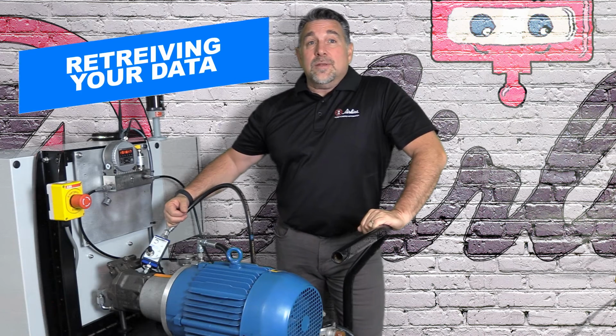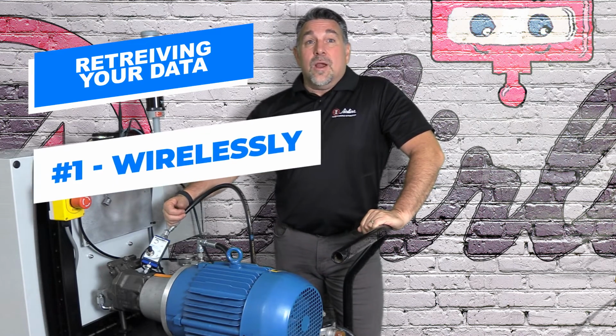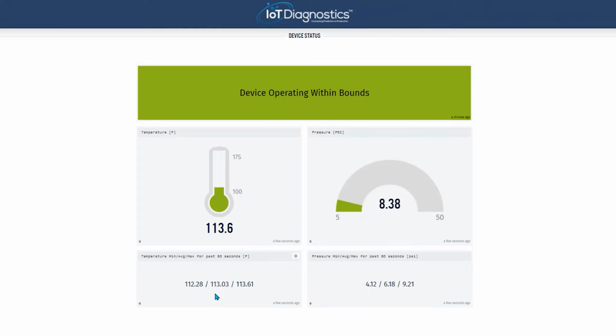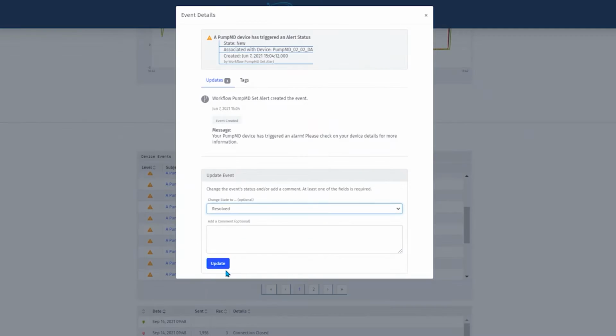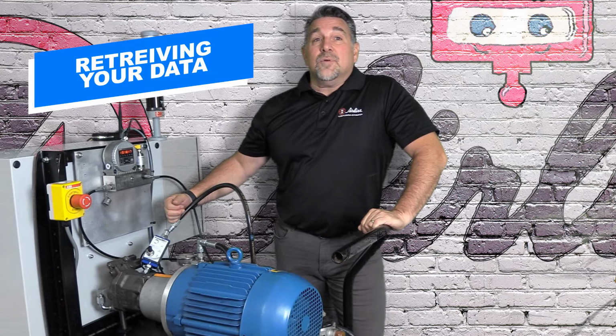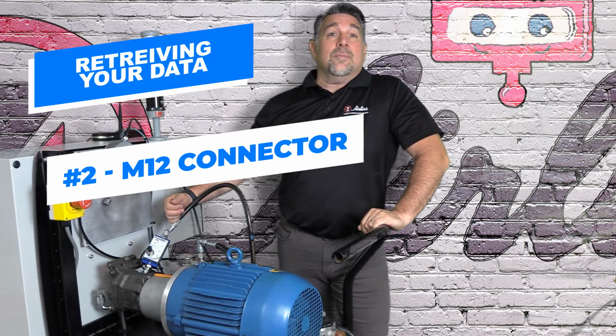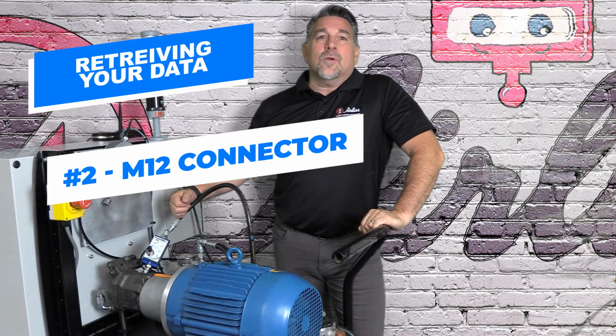You can retrieve your process data from the PumpMD one of two ways. The PumpMD connects wirelessly to the IoT Experience Cloud Service. This service provides a graphical view and logging of your data. The PumpMD also provides two 0 to 10 volt DC analog signals through the M12 connector. These signals can be connected to any PLC or other monitoring device.